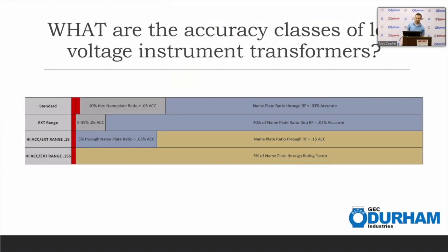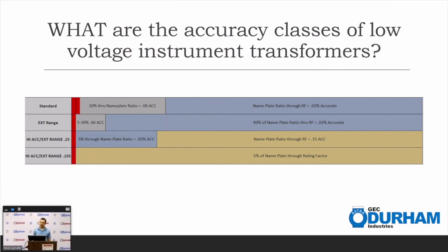So what are the accuracy classes? There's more or less 3 numbers that we deal with, but there are multiple types of accuracy classes. We kind of bunch these into 4 main categories. So you have a standard, you have an extended range transformer, you have a high accuracy extended range transformer. These are 0.15 accurate. And then there's also a high accuracy extended range 0.15S transformer. So the ANSI guidelines for the test points of these are all different, and they're able to perform better at different levels. Obviously, there's a different cost for each of these, but we're going to look into a little bit of these as we go. But just want you to keep in mind there's a 0.3 accuracy range and a 0.15 accuracy range.